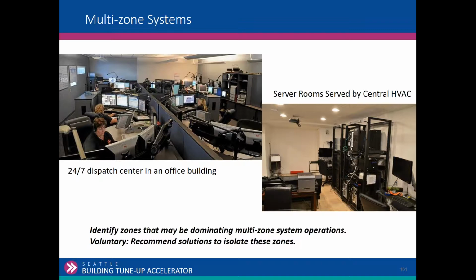Multi-zone systems, it's a voluntary thing, but identify any zones that are dominating multi-zone. We talked about this, I call it a rogue zone. So, the computer room that's demanding 55-degree air, the VAV box is 100% open, 24/7, never closes down, which is not allowing your main air handling unit to reset above 55, because I've got this constant cooling demand. A recommendation, hey, maybe we should replace the VAV box, need more air here, so it'll throttle, or provide a separate system. We need a ductless mini split in there so that we can implement a reset schedule.